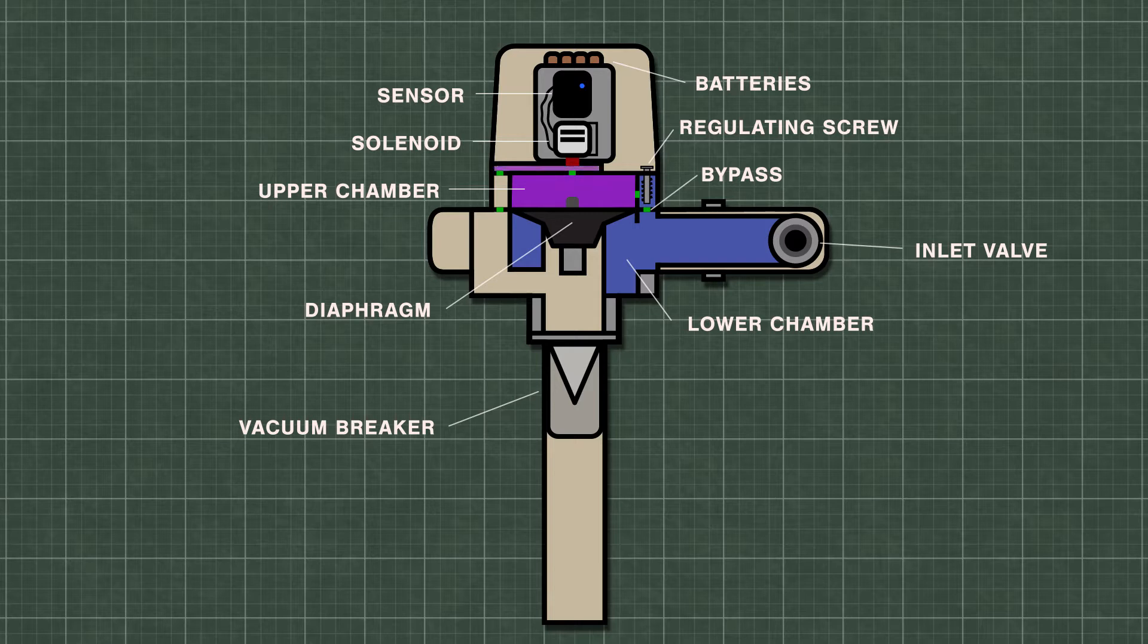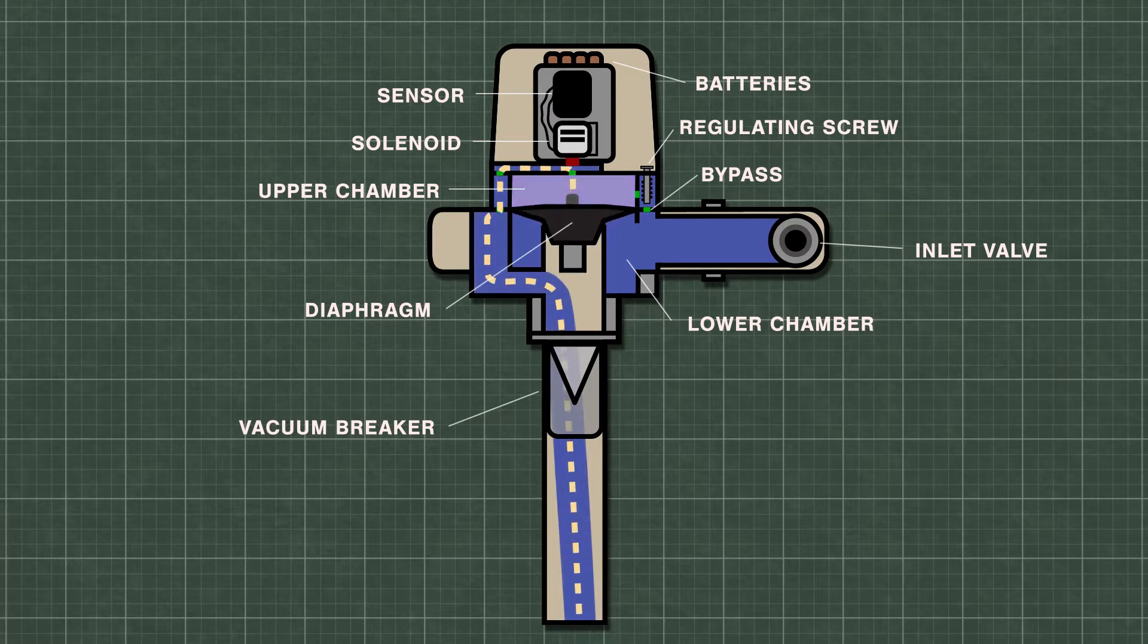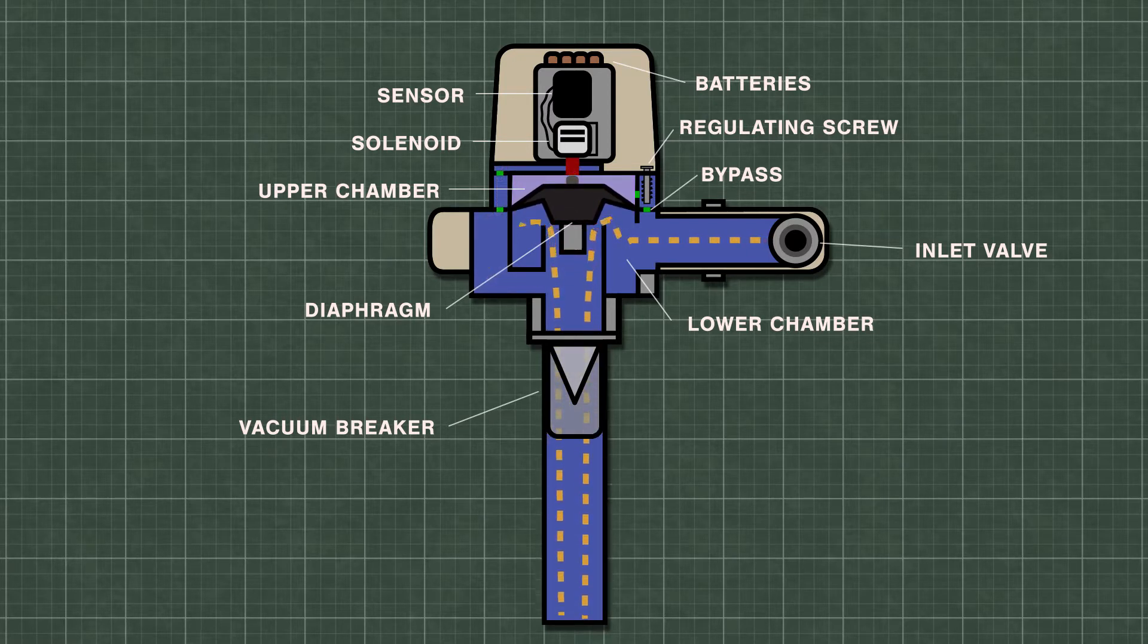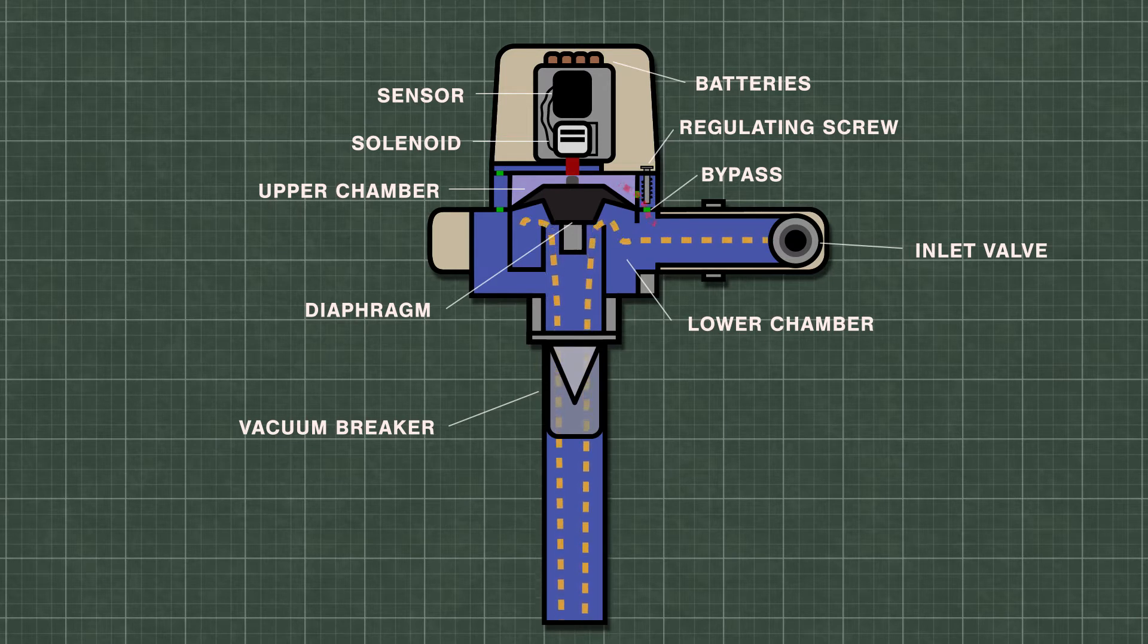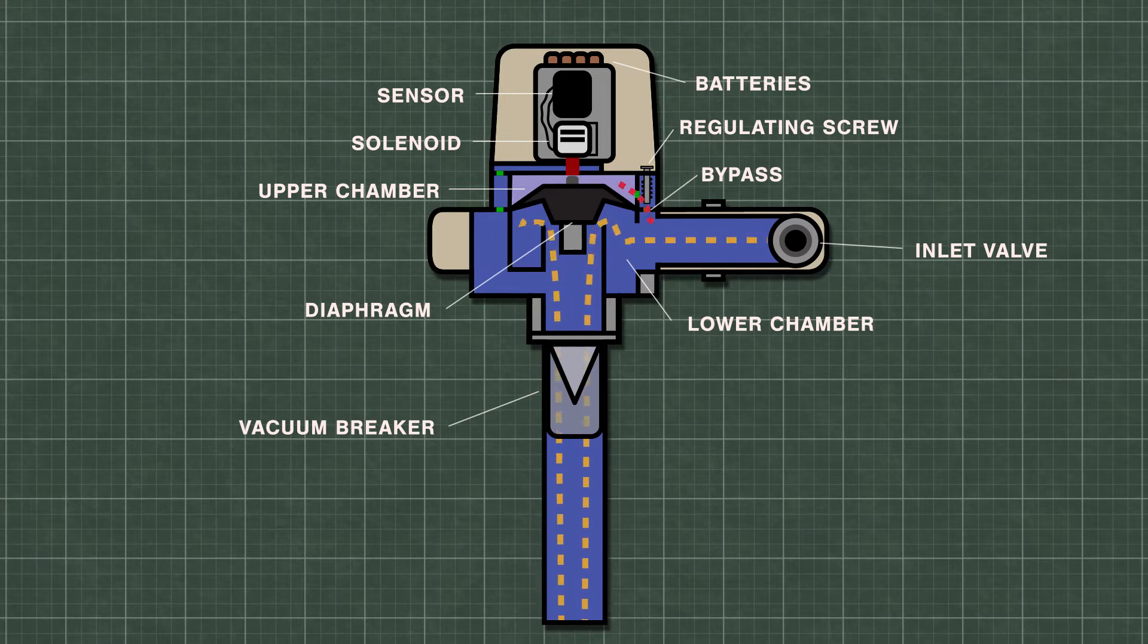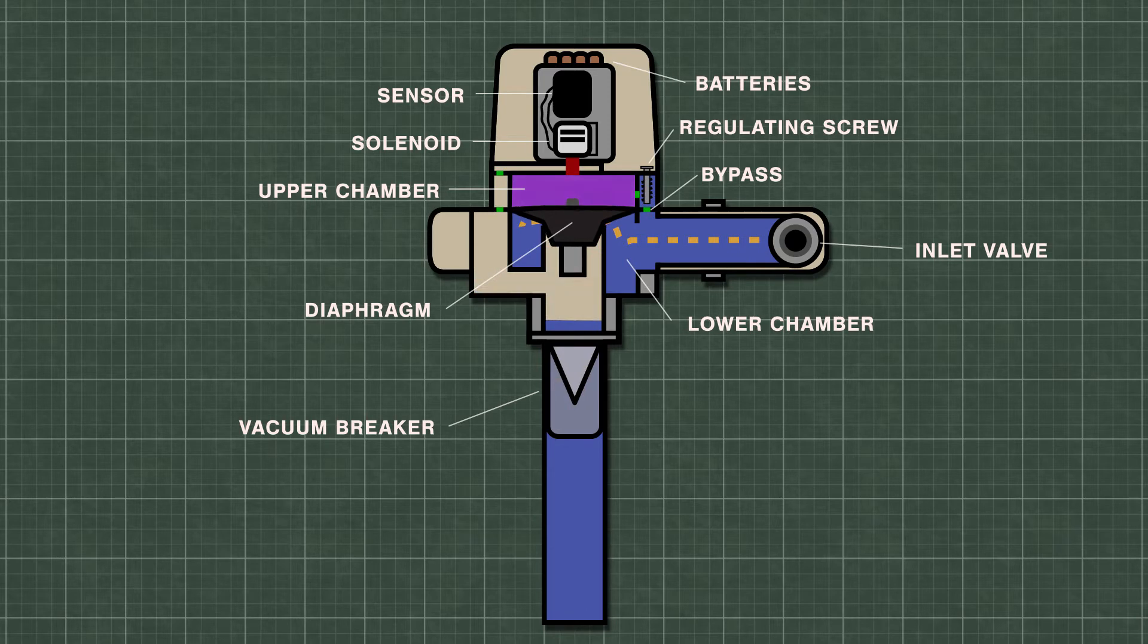When the sensor is activated, the solenoid valve opens and releases water from the upper chamber. This creates a vacuum which lifts the diaphragm up from the valve seat. The water from the inlet then travels down the flush pipe. As the water flows, some of the water slowly travels through the bypass and will eventually fill the upper chamber. The flush will continue until the pressure pushes the diaphragm down once again.